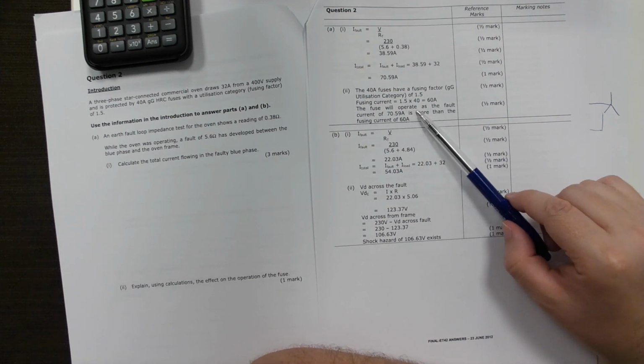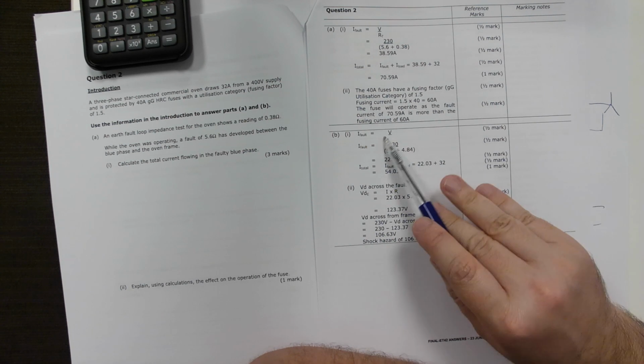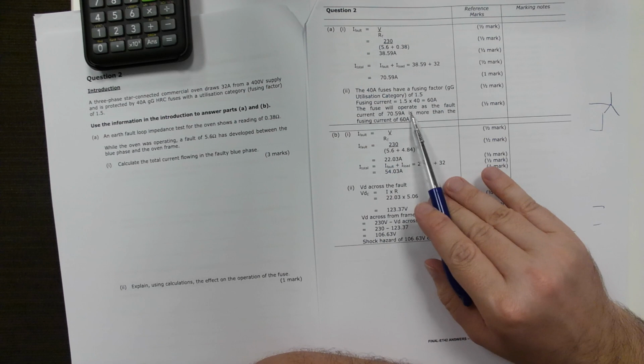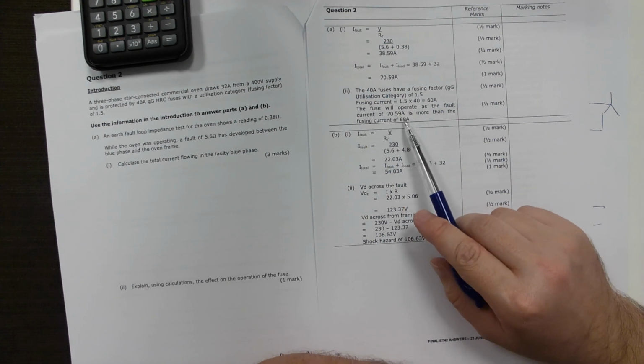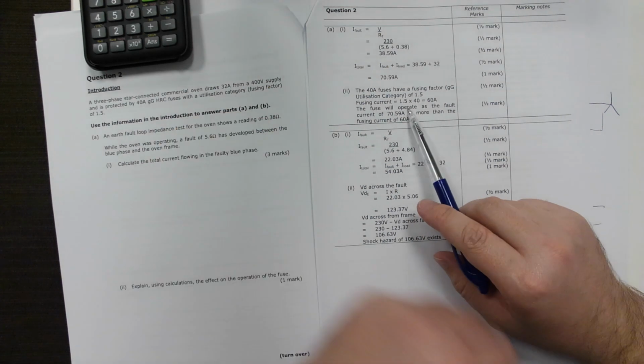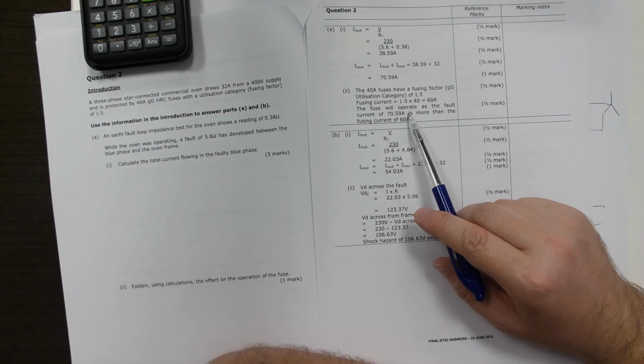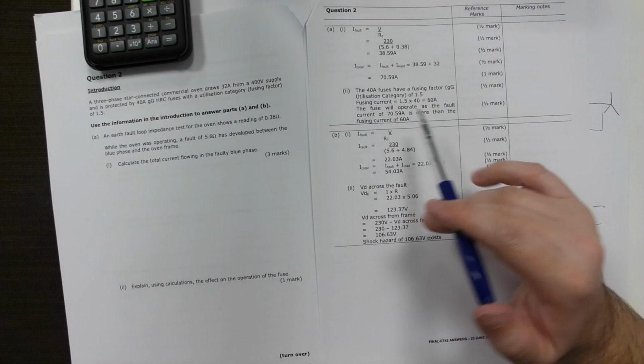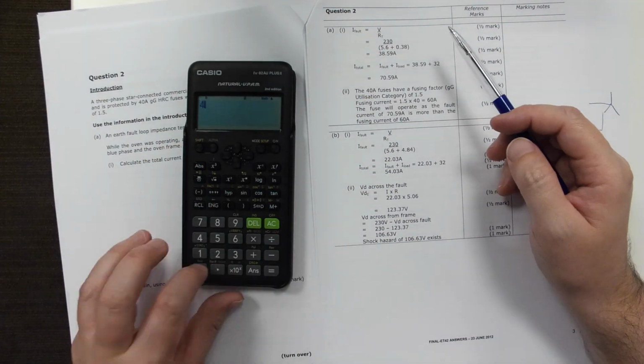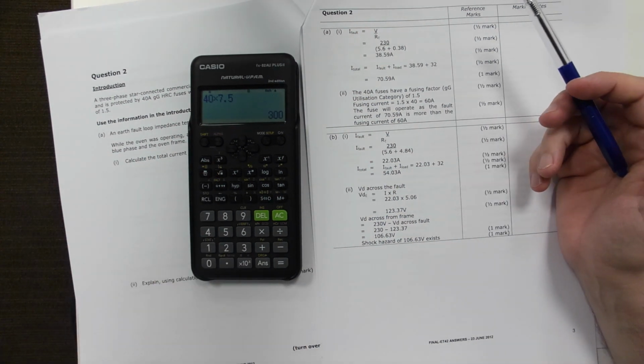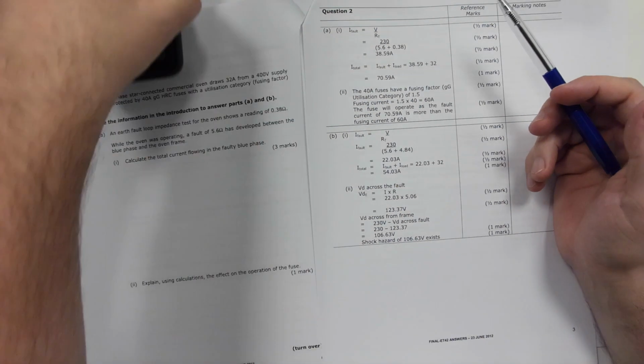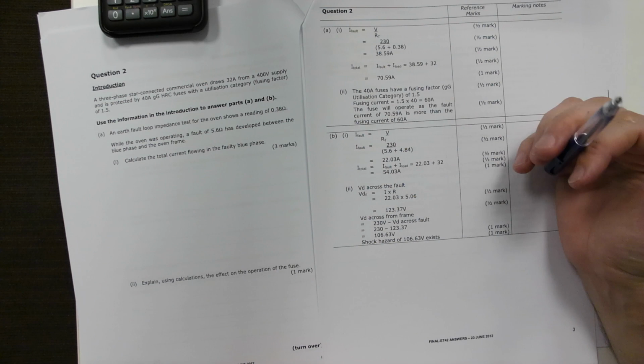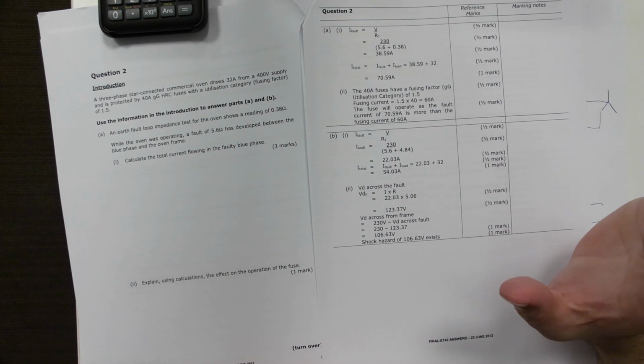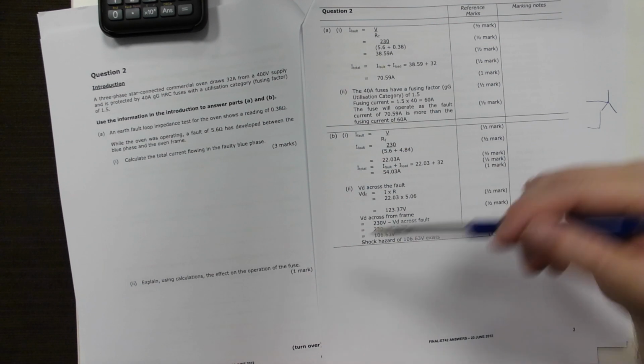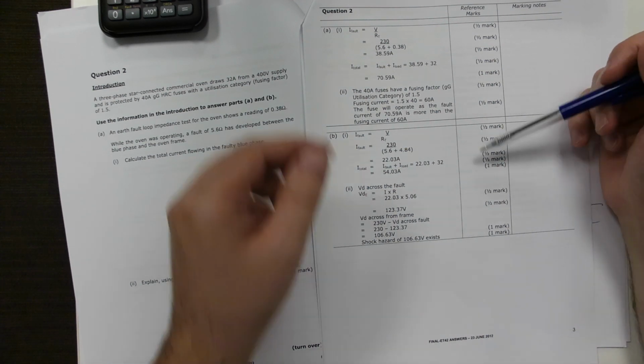The fuse will operate as the fault current of 70.59 amps is more than the fusing current of 60 amps. So it is going to melt. It's just a question of how quick, because this is an overload, not a short circuit. A short circuit on a GG fuse is typically 7.5 times its rated current, so 40 times 7.5 would be 300 amps. So we're not expecting an instant loss of power, or less than 0.4 of a second, which is the legal minimum. What we are actually expecting is a slow fizzle that could take an hour or two. So not an instant disconnection of supply.